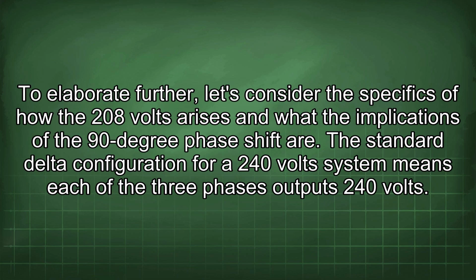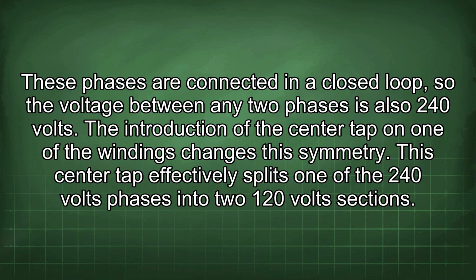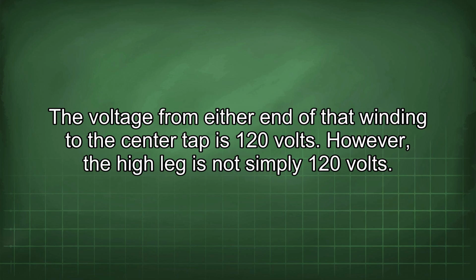To elaborate further, let's consider the specifics of how the 208 volts arises and what the implications of the 90-degree phase shift are. The standard delta configuration for a 240 volt system means each of the three phases outputs 240 volts. These phases are connected in a closed loop, so the voltage between any two phases is also 240 volts. The introduction of the center tap on one of the windings changes this symmetry. This center tap effectively splits one of the 240 volts phases into two 120 volt sections. The voltage from either end of the winding to the center tap is 120 volts.